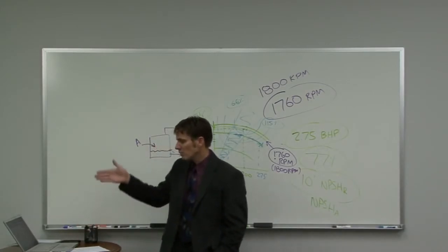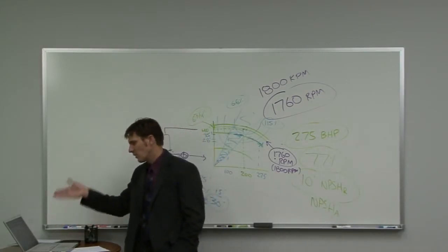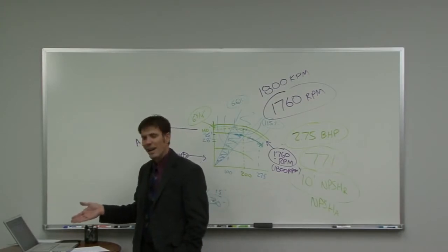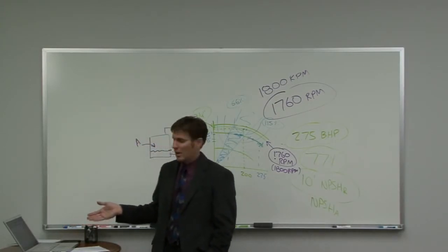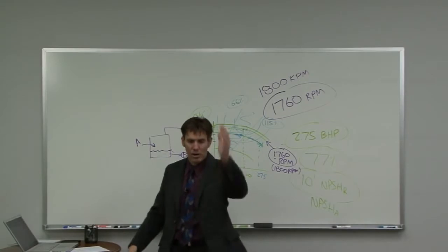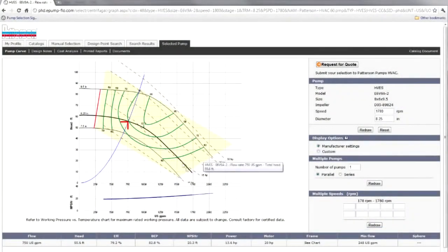But a lot of engineers don't consider that, and they look at this and say, well, I want a 20 horsepower. When in reality, they probably will never even operate there, unless they break the pipe somewhere and it's blowing out to atmosphere. But even with this pump blowing out to atmosphere, it would pull us back down into the 15 horsepower line. So these are things that have to be evaluated.